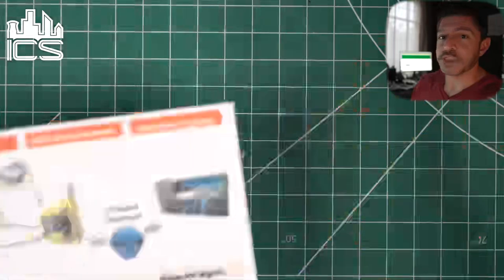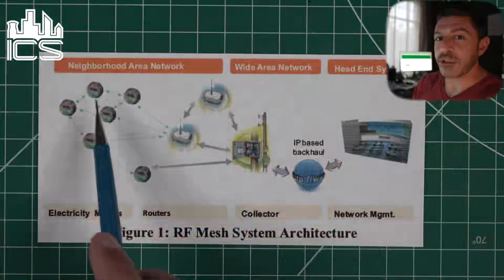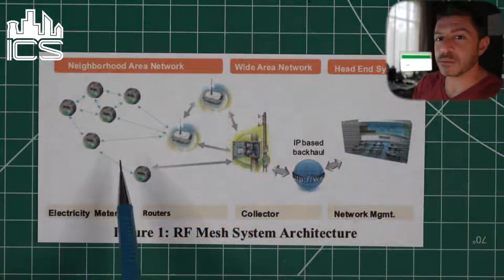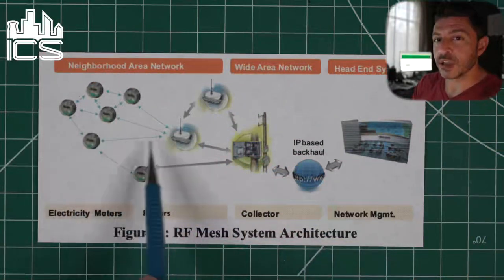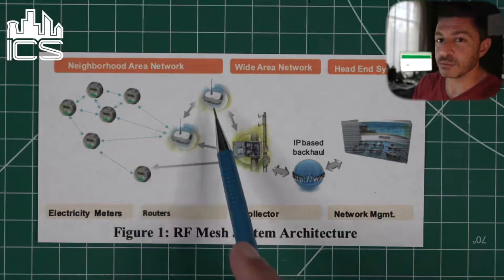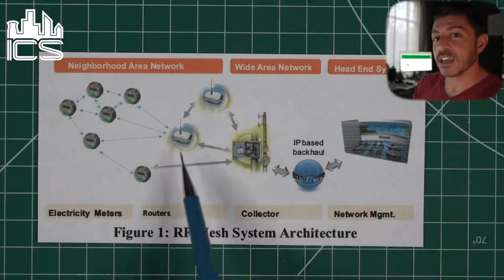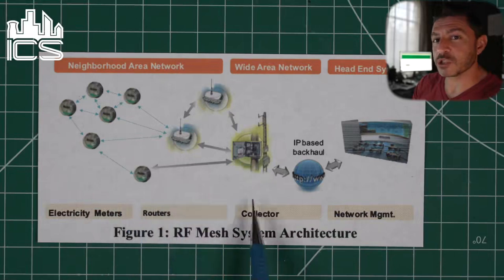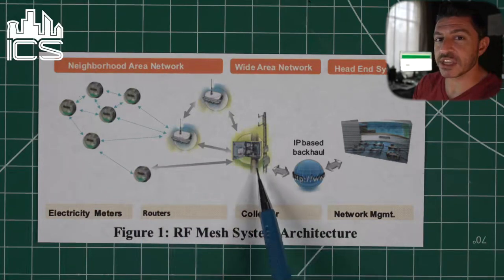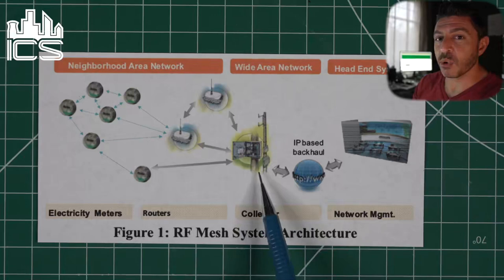So you can see here it shows all the meters, they send their messages, they relay them between them, so it really forms a large mesh network. But then it has to get off of that mesh and it goes up to what they call a router, like the device I showed earlier that's actually a collector. Then it goes to what they consider kind of a traditional collector. This is a device sitting inside of a substation, usually with a big pole and two to four antennas on it.